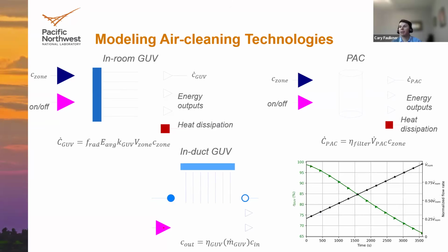In this case, the inactivation efficiency is closely related to the airflow rate because, for example, these in-duct UV systems are going to irradiate some space within the duct, and the pathogens will be inactivated based on how much time is spent in that irradiated space. So if the airflow rates are really high, the airflow is moving past it very quickly, less time will be spent in that irradiated space compared to if the airflow is moving more slowly.